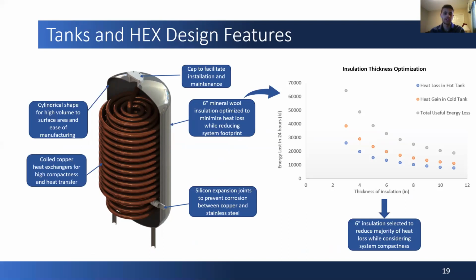And this 6 inches was determined by plotting the relationship between the heat lost and the insulation thickness. After 6 inches, we realized that the majority of the heat lost is reduced. However, we didn't want to continue adding thickness, as this would make our system very, very large. So we had to consider both compactness and efficiency here. Also, caps were installed on both tanks at the top to facilitate the installation of the PCM materials.